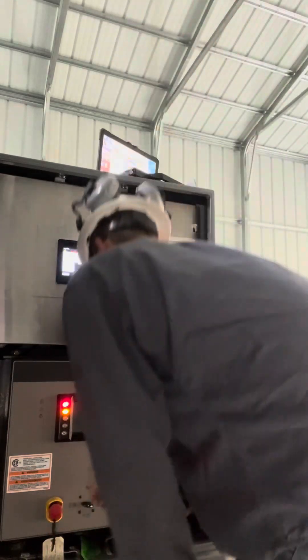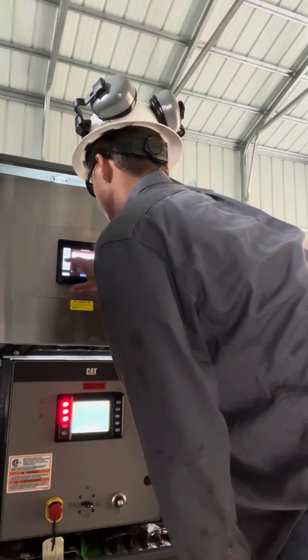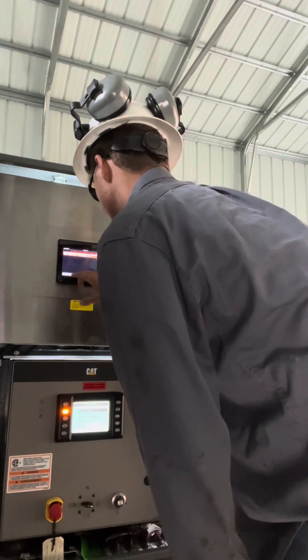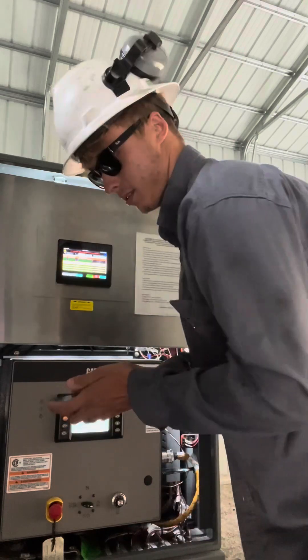Right now we're inside the compressor shed. First thing I'm gonna do is close this suction wheel. That is closed. Then we go over here to the RTU in the compressor shed and we're gonna check some stuff out. Usually if it doesn't tell you exactly what it is on the top screen, then you have to use the CAT panel on the bottom — and it gives you what you'll want to see. Low suction pressure, and see the time, 7:47.